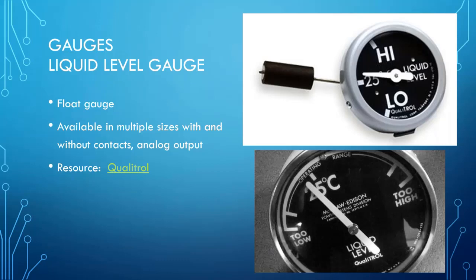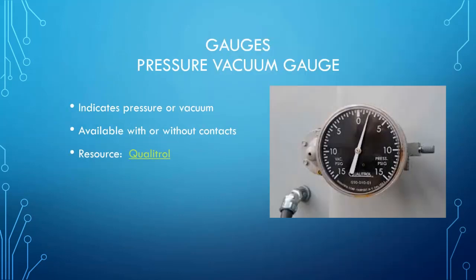Most of them are just a float that detects the oil level. Now these range all the way from $15 to a couple thousand. They're as simple as a float gauge, and they get up to as complex as analog outputs, digital outputs, switches to close and open contacts when the level gauge is too low. I've put a link to Qualitrol's website in this slide, and you could spend all day educating yourself on these gauges. This is what a pressure vacuum gauge looks like.